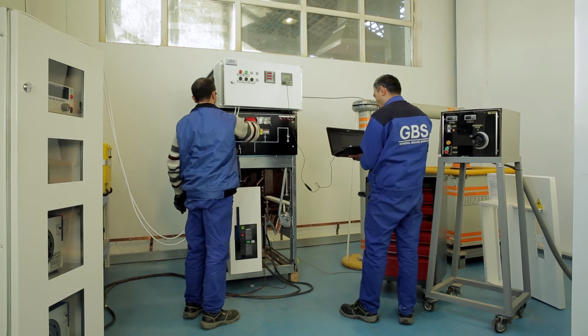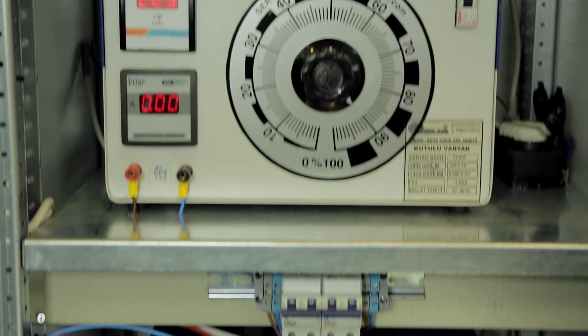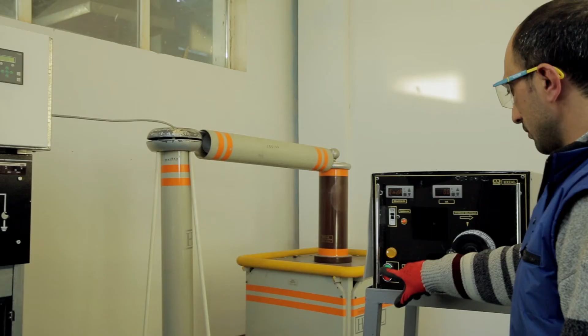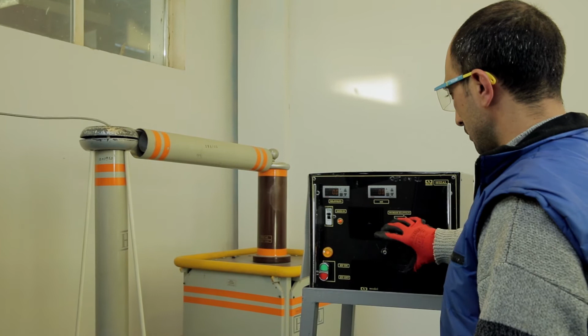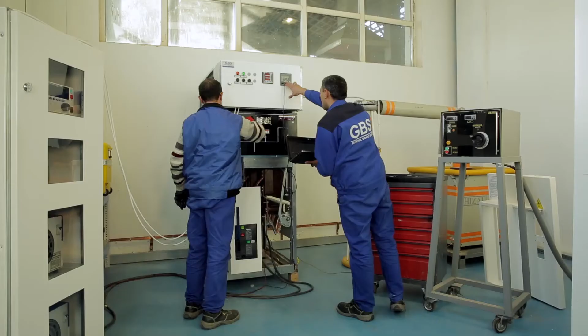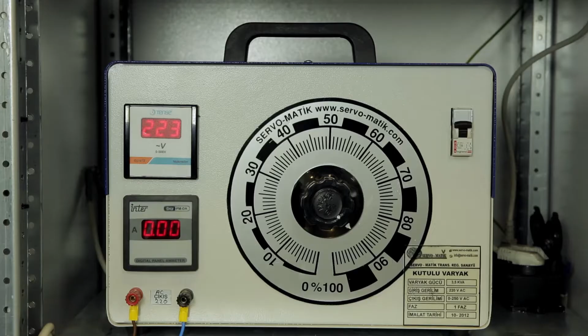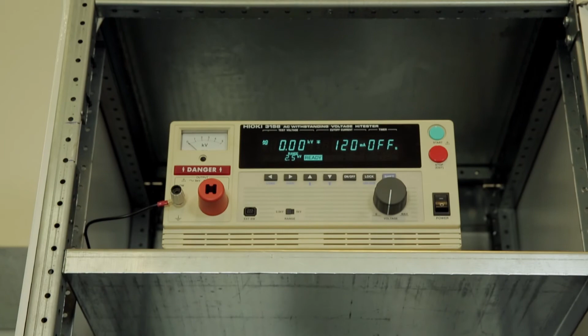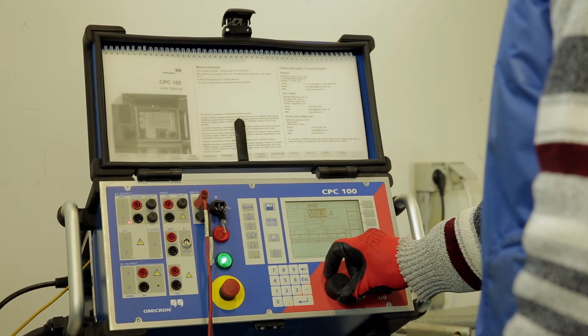The visual examination is followed by the examination of mechanical operability. Then, dielectric tests are conducted and insulating resistance tested. Safety tests are conducted. High-voltage tests are intended to examine the reliability of insulation, as well as possible defects in visible cracks and current leakage using measurement equipment. The products are then packaged and handed over to the finished products warehouse for delivery to customers.